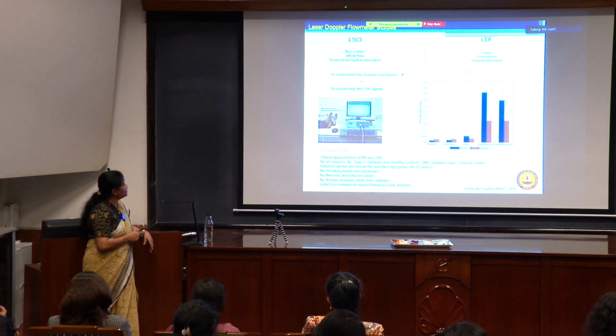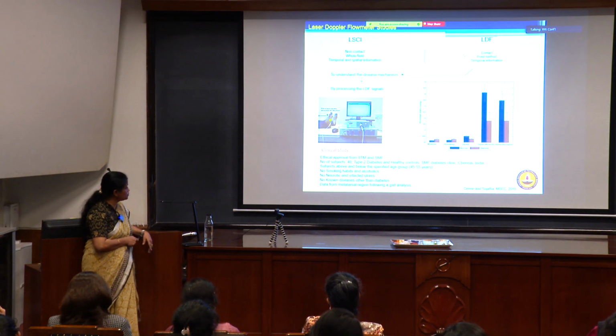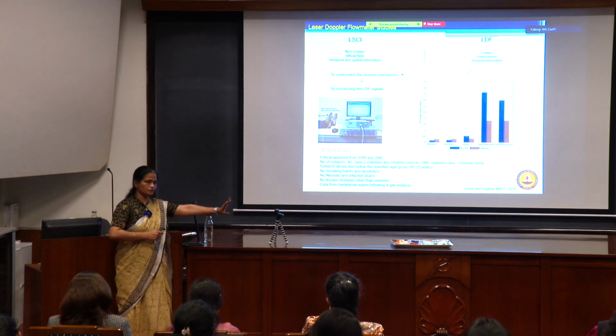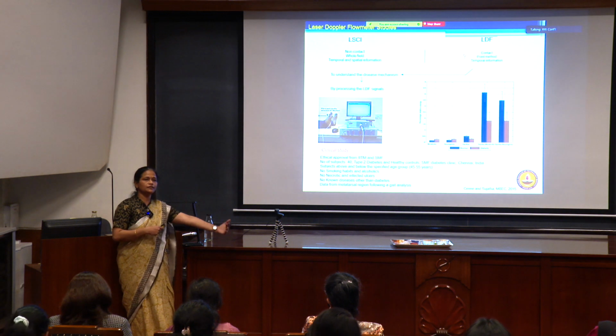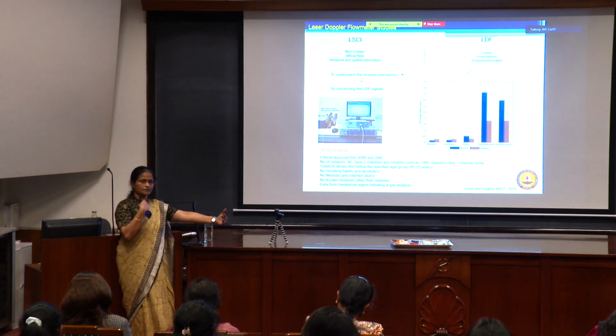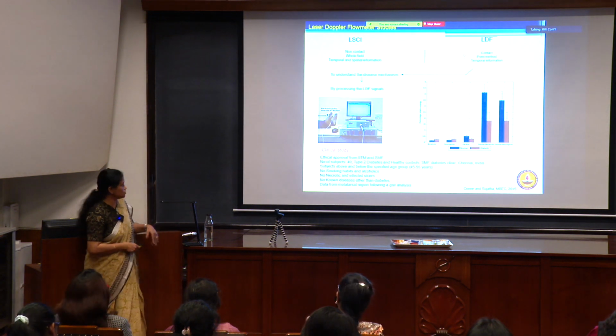The second one is the shift in the frequency. This is also a very convenient thing to use. This is a Doppler probe which is attached to the foot of a patient, and then you get a continuous perfusion signal. It is based upon the shift in the source frequency. When there is a moving phenomenon, the return light has a shifted frequency as compared to the source frequency.